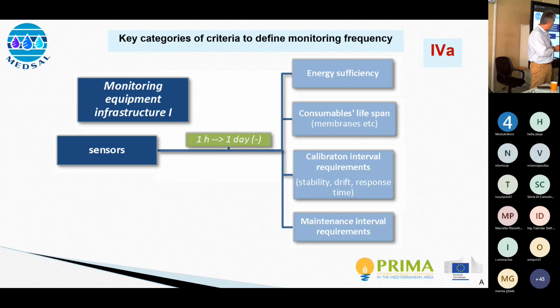Calibration interval requirements: you select how often you monitor based also on this parameter - what's the stability window, what's the drift slope of the sensor, and what's the response time of the sensor and the outcome.